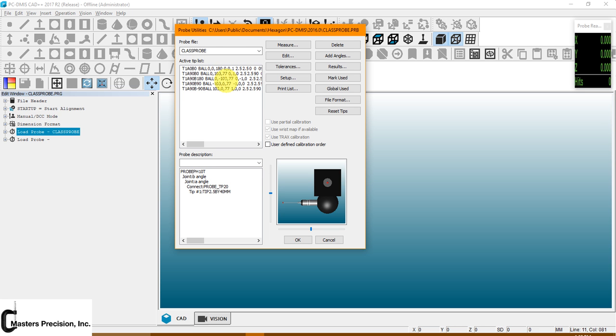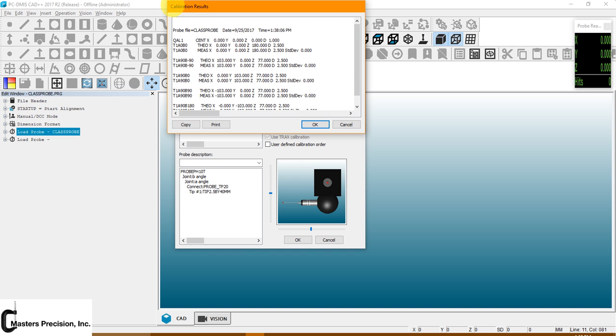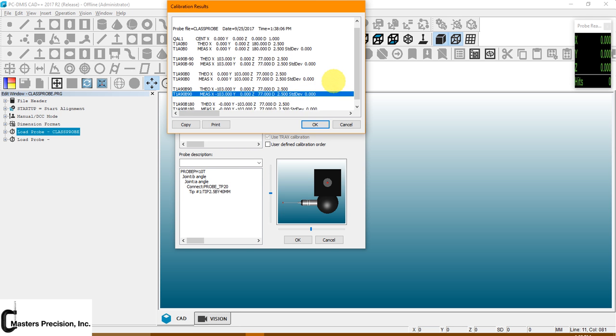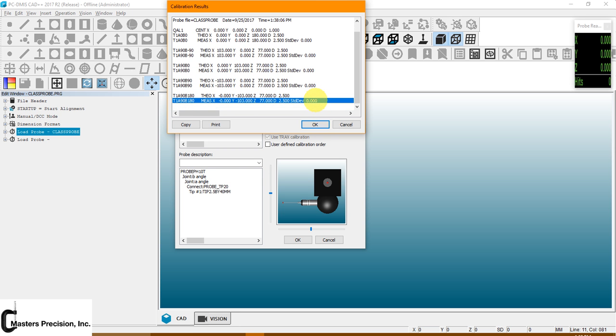To see the results of these, while you have the probe file still in the same one that you've calibrated, go to results. You'll get the calibration results. And here's our standard deviation, which is what you're looking for. Now, since I'm in millimeters, anything up to 5 thou will be considered acceptable. Anything over 5 to 7 thou, it would just make me feel more warm and fuzzy if you were to go ahead and try to dial that in a little bit.